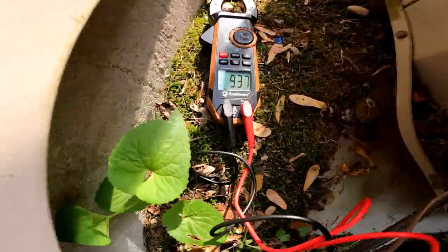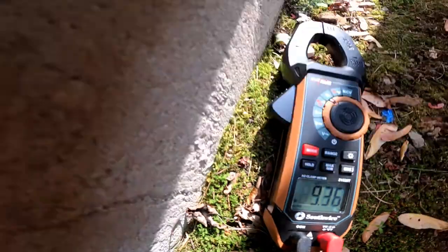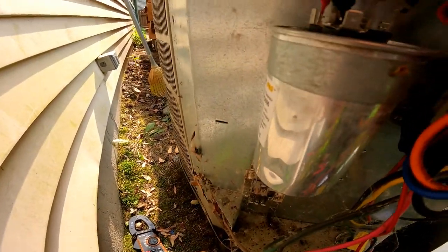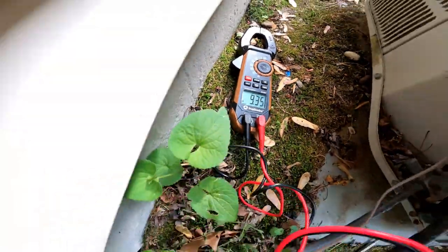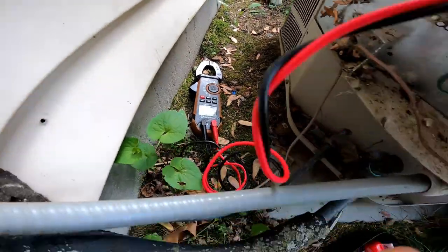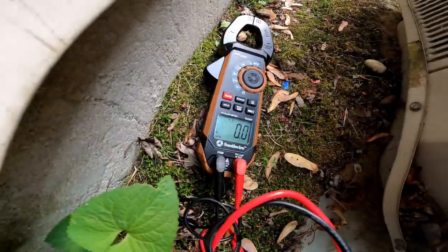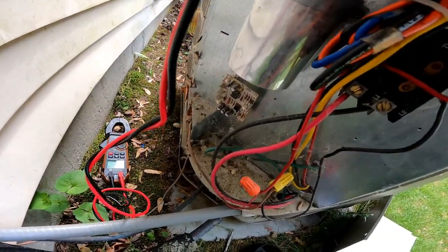All right, and right there, we've got 9 microfarads between the common and the Herm. Okay, 9 microfarads, which is definitely not 50, and it's definitely not 5 either. So let me just go ahead and pull it off. I'm going to reset it back to 0, and I'm going to hit it again. And I think this is going to be the issue.